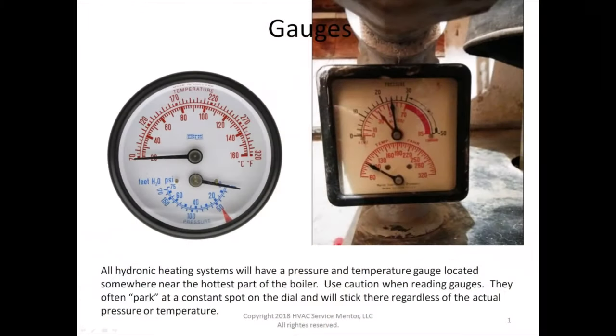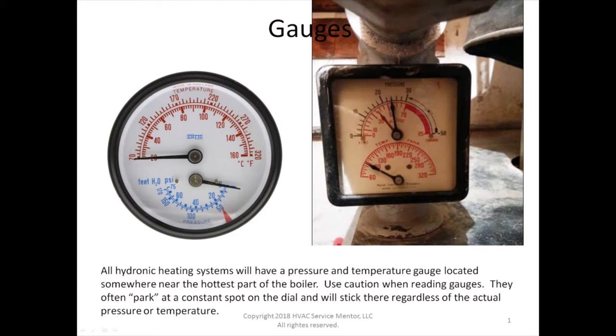When you first arrive on a job site, one of the things you need to concern yourself with is: what is the pressure in my boiler system? All hydronic heating systems are going to have a pressure and temperature gauge located somewhere near the hottest part of the boiler. Use some caution when reading these gauges because they can often get stuck in a constant spot on the dial regardless of what the actual pressure or temperature is. Once you've verified you can rely on your gauges, this is where you'll find that information.